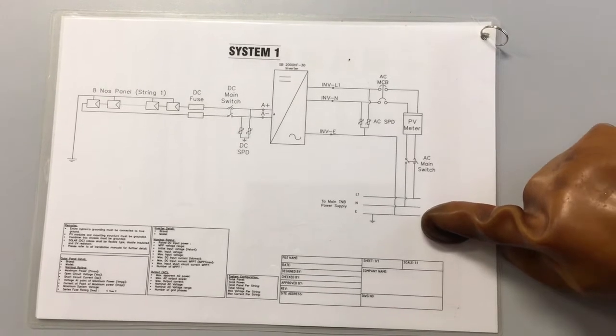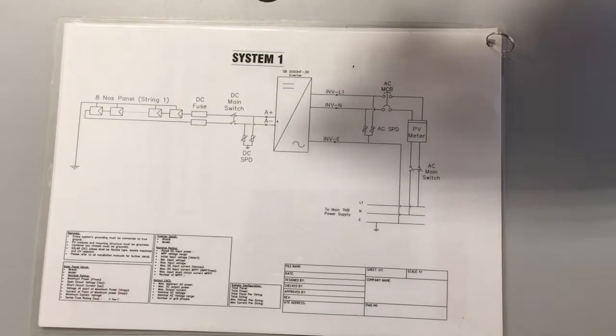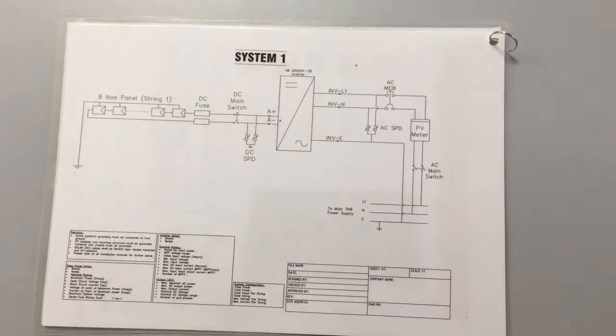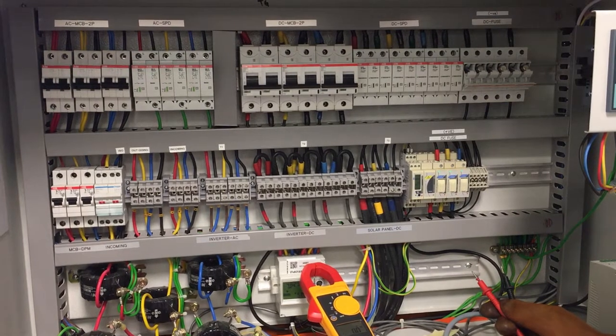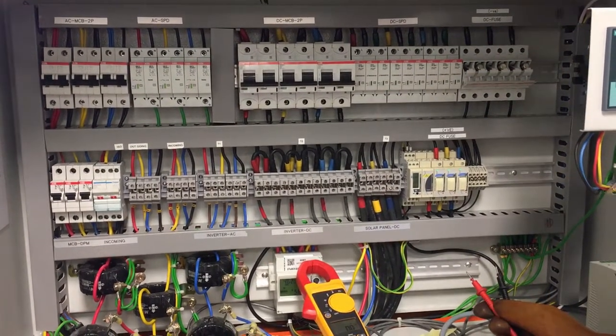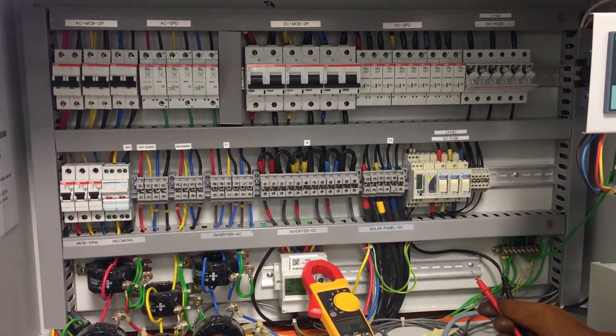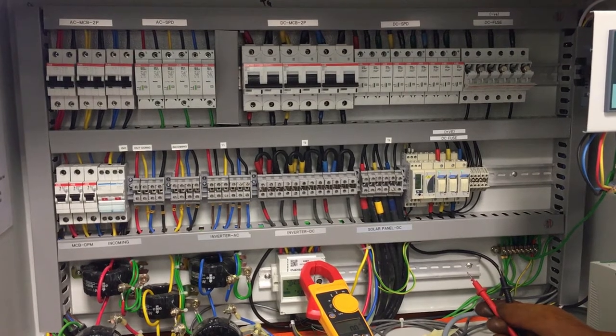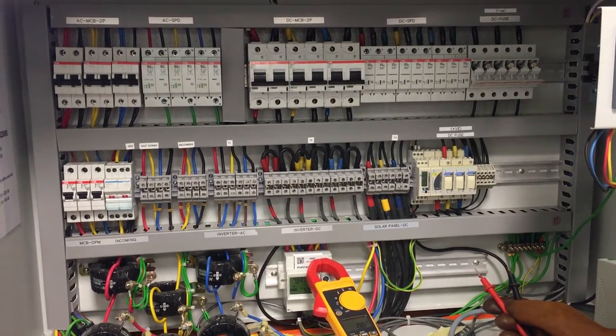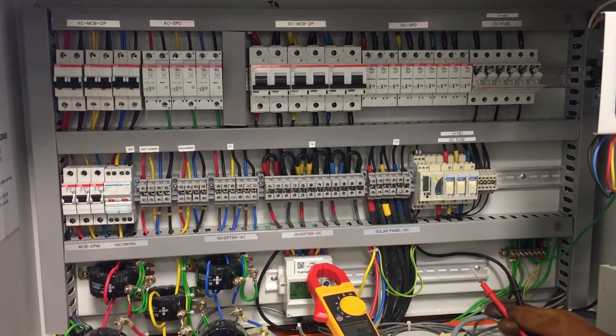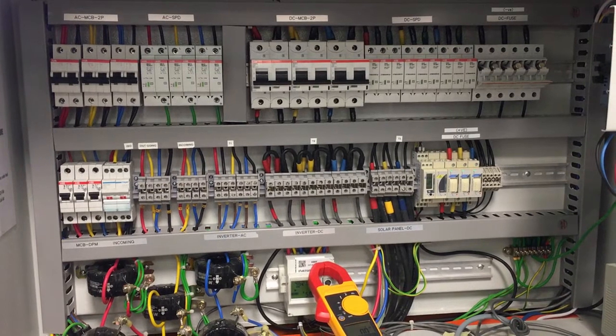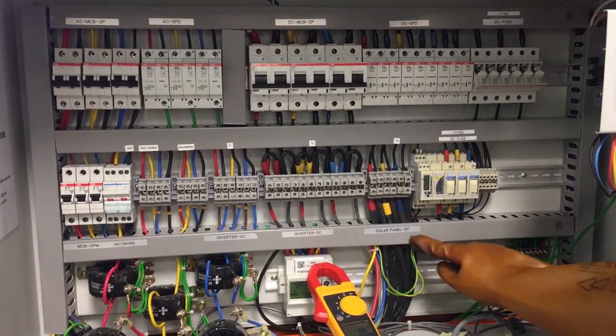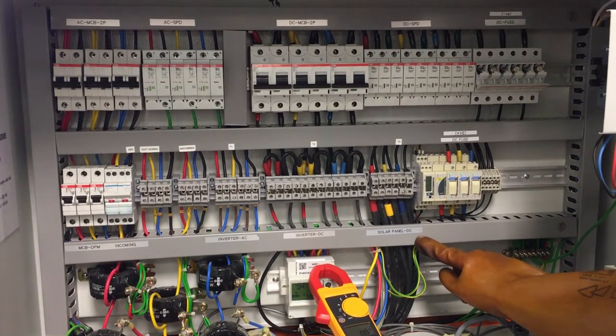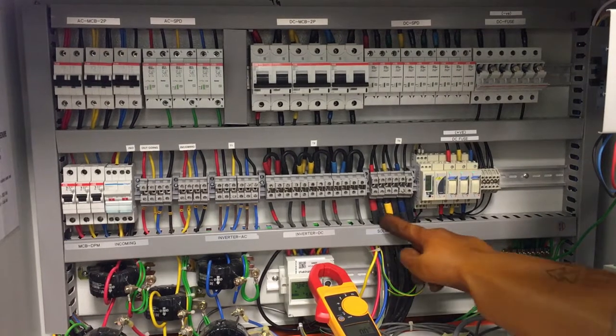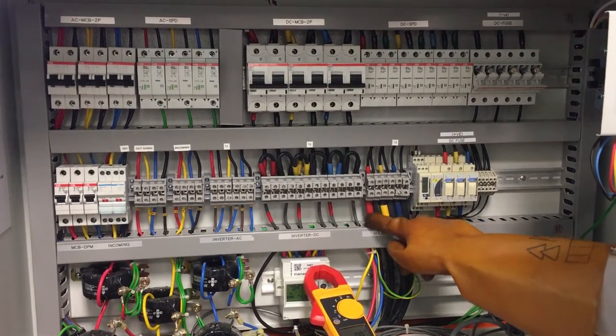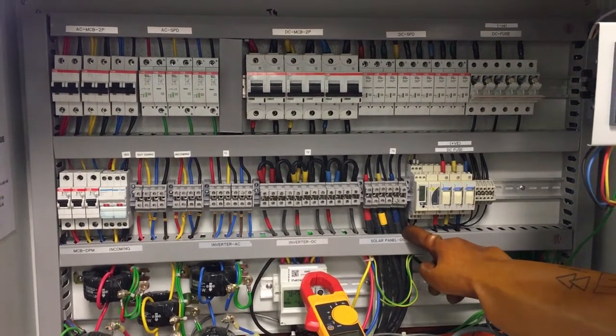Now we are going to look at the system and match it with what we see from our single line diagram. From the single line diagram, this is the actual configuration in the array junction box. Because it's already completed, you can see the labels. But if you do not see the labels, you should also be able to identify. These are the cables from the solar panel. The way you can know is that the cable itself is different. It is quite thick and dark in color. These are usually DC cables, solar cables.